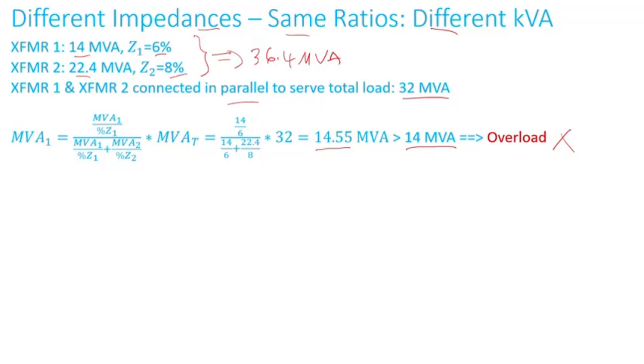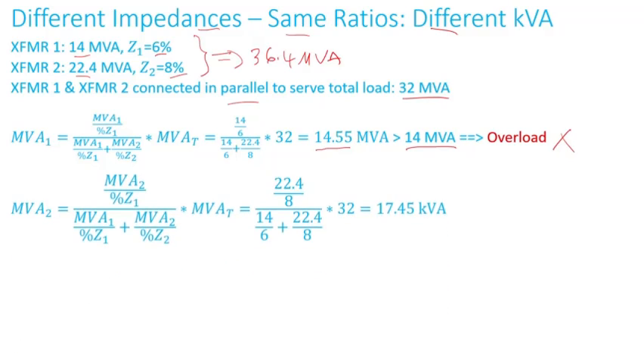At 88% loading of the combined capability of both transformers, transformer one is already overloaded. Applying the same equation to transformer two, I get 17.45 MVA, so transformer two is not overloaded.